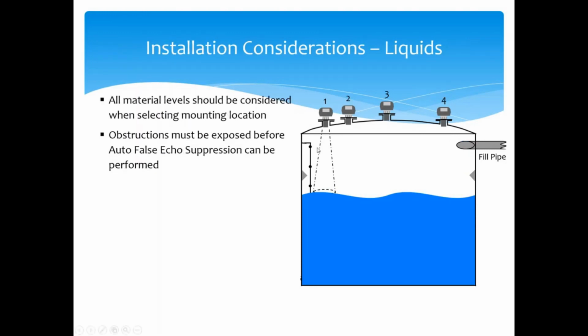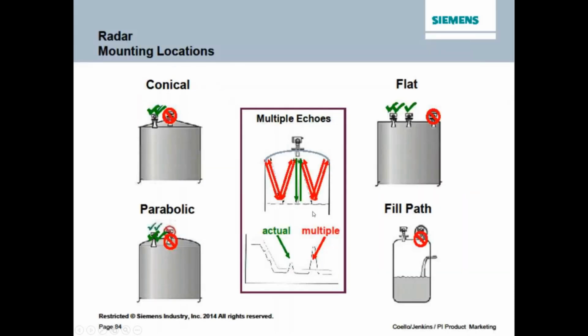Showing you here how number 1 will work great in certain scenarios, but as the liquid level goes down towards the bottom of the tank, you're going to start to have issues with that ladder or sidewall. This is a depiction of a signal return when you're mounted in the dead center of a dome-topped tank. Your primary echo might have a certain amplitude, but the secondary echo reflected off that dome top is significantly larger, so the instrument would want to pick up on that secondary echo. That's why we wouldn't want to mount it in the dead center. If we did mount it in the dead center in an application like this and noticed our secondary echo was larger, we'd change our algorithm to F, for first, and pick up on that first echo profile above the threshold.